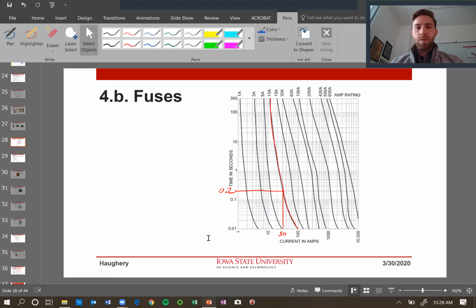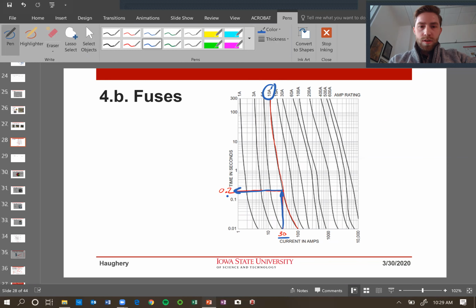Looking at fuses, similar process to interpreting their trip curves, except we have different curves per the different currents that we have. So if we had a 10 amp fuse and we have 30 amps of current going through that fuse, it will trip in about 0.2 seconds, is what we determined. So again, you're following up vertically until you hit the curve and then going over horizontally until you find that time. You could do it the other way, from Y to X. So if you have a certain amount of time, how much current can you withstand for that amount of time? You could do it that way as well.